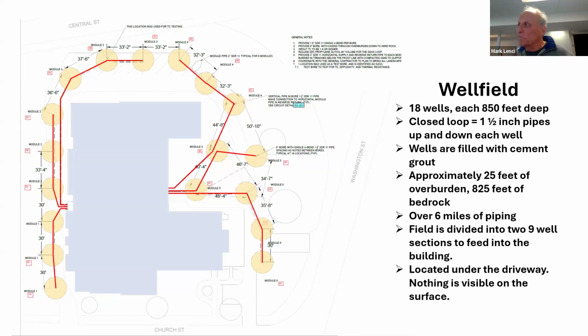These are forever underground and you never see anything of them once they're drilled. It's extremely intrusive during drilling, probably looks like Dallas oil fields when this comes in, because there's 18 wells, 850 feet deep. They're closed loop, meaning you drill a 6-inch diameter hole 850 feet down into granite. For us, that means about 25 feet of overburden and then 825 feet of bedrock. Obviously you want bedrock as soon as possible.